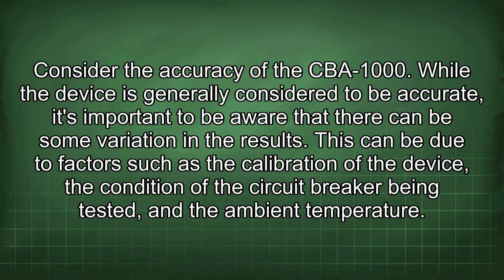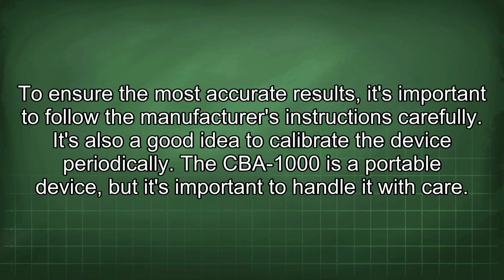Consider the accuracy of the CBA-1000. While the device is generally considered to be accurate, it's important to be aware that there can be some variation in the results. This can be due to factors such as the calibration of the device, the condition of the circuit breaker being tested, and the ambient temperature. To ensure the most accurate results, it's important to follow the manufacturer's instructions carefully. It's also a good idea to calibrate the device periodically.